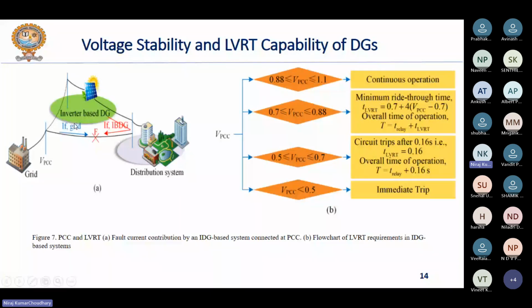So here you can see the voltage of the PCC bus, the range is shown like that. If it lies between 0.88 to 1.1, then there will be continuous operation. It means there is no fault in the system. If it is slightly below unity, 1 per unit, it means that load may have increased in the system, due to which there is some voltage drop in the system. And if the load decreases, then there will be a voltage swell condition, means above 1 per unit condition. So there will be continuous operation of the DG.